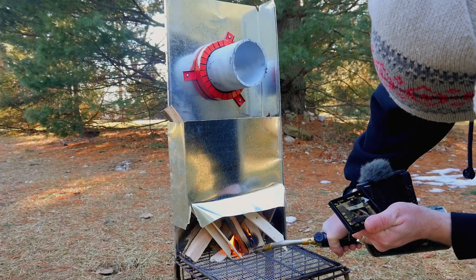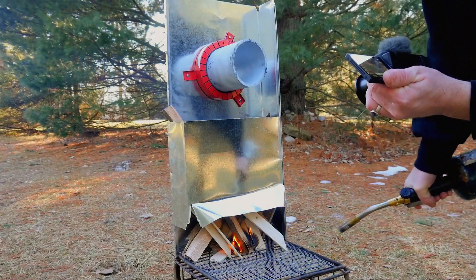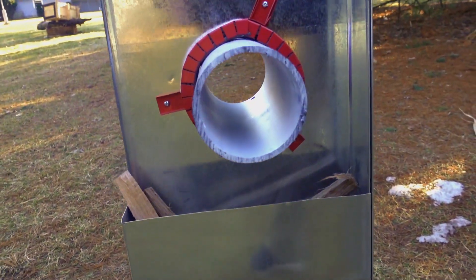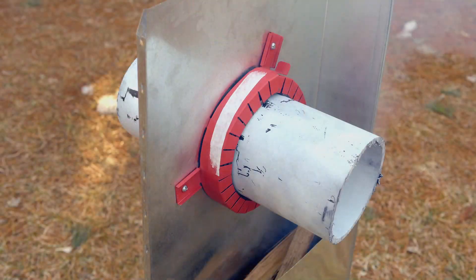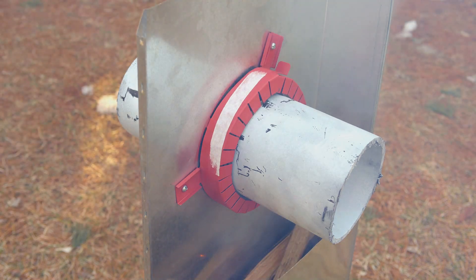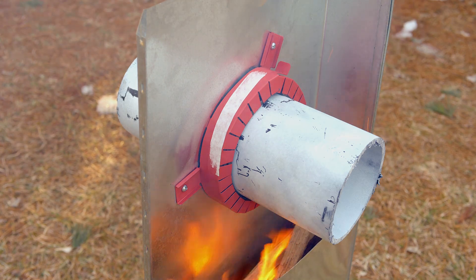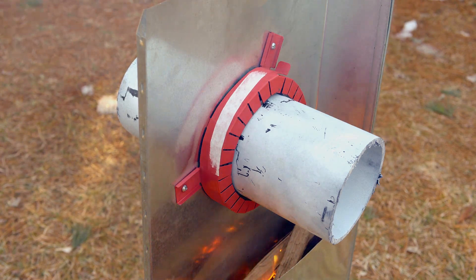To test this collar we'll light a fire in my sheet metal contraption and observe the result. In this test I am using high-density polyethylene pipe, which is a non-chlorinated plastic. I picked this plastic intentionally because the byproducts when it burns are comparatively less harmful than more common plastic pipe like PVC.